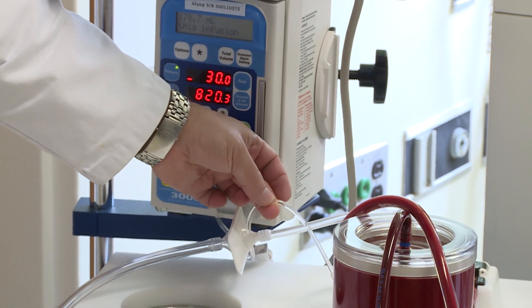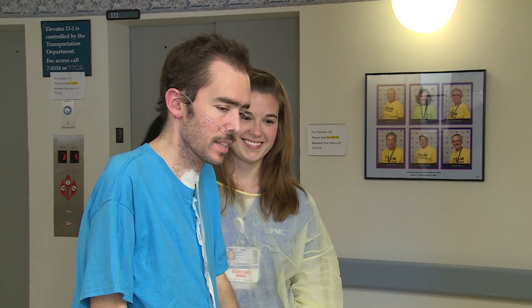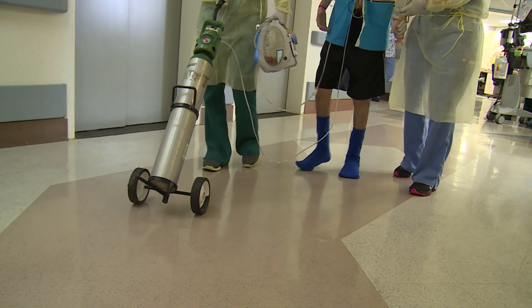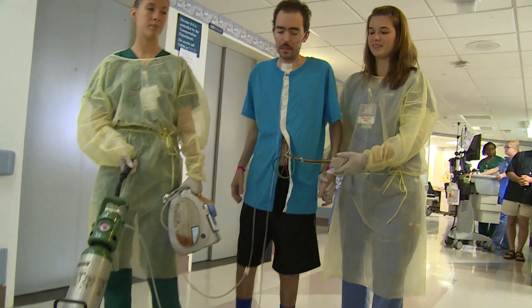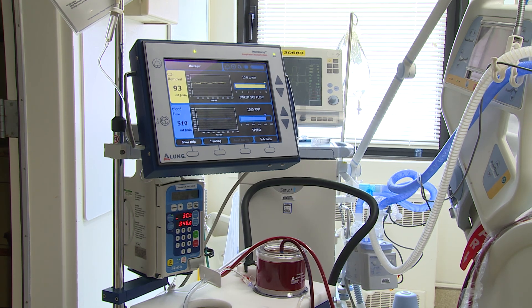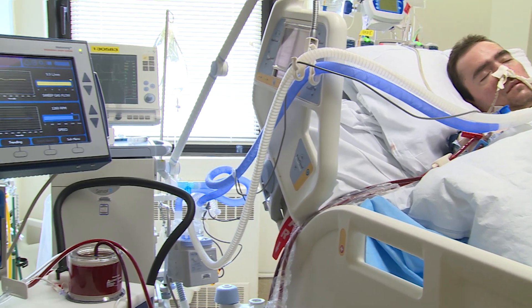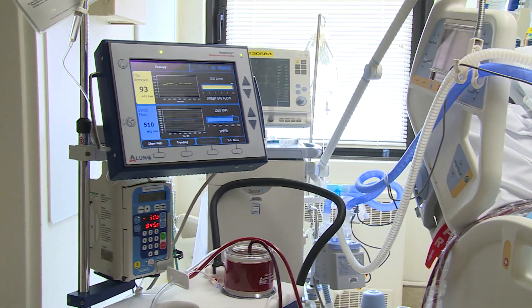It worked instantly. The Hemolung brought his CO2 down to wonderful levels, very manageable, and all of the nurses and the doctors and the perfusionists were all very astounded. It's the first time it's been used in the U.S., so no one had seen it. It's basically an oxygenator that runs blood through it. The main objective of this device is to clear CO2 — it has a little percentage of oxygenation, but mostly CO2 removal.